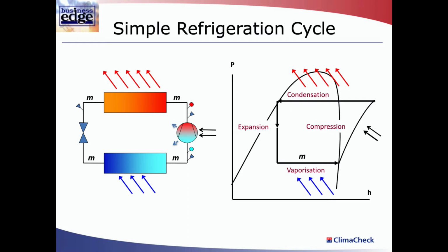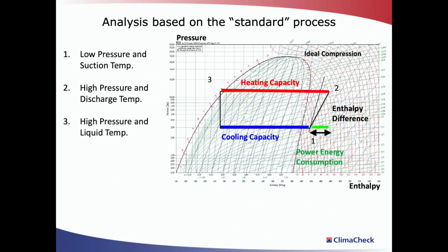It's a very useful technology for troubleshooting, performance analyzing, getting your refrigerant charge right, adjusting your TEVs, economizer TEVs, and so on, all of which are pretty much impossible to do within field constraints. Where blend refrigerants are concerned, it's almost impossible to work out the midpoints and so on quickly enough to determine what's going on. ClimaCheck does all of this for you.